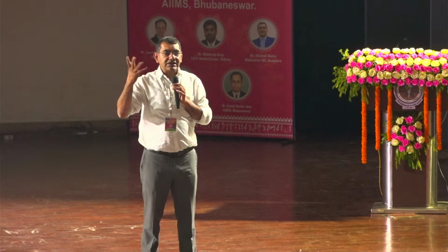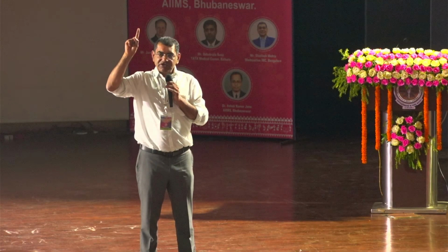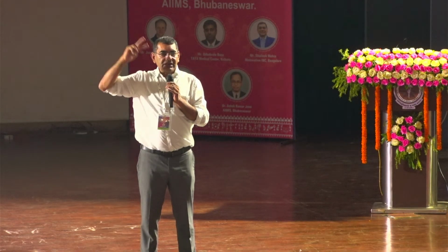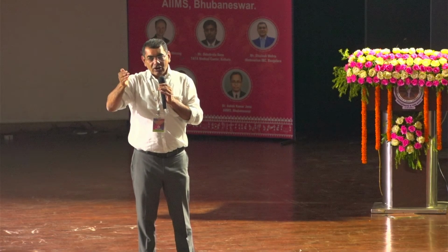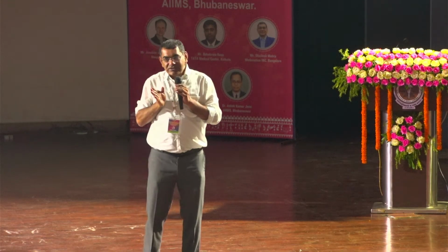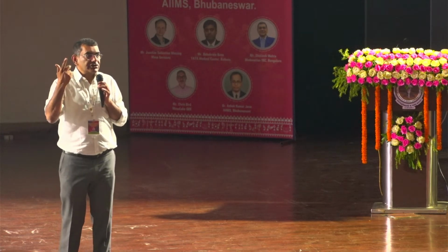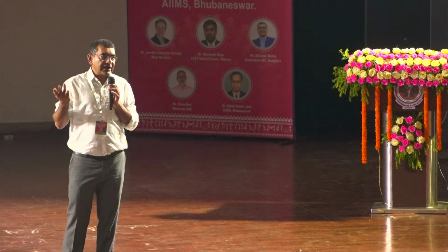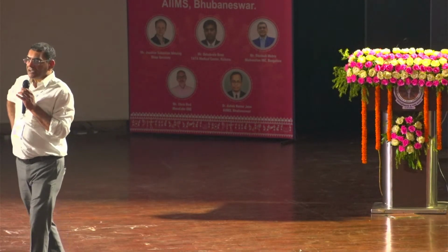इन्फेक्शन कंट्रोल. विदाउट दिस यू बीइंग इन्फेक्शन कंट्रोल इज अ वेस्ट. भुवनेश्वर का प्रेशर कितना है? एटमॉस्फेरिक प्रेशर 1. मिस्टर मेत्सिंग ने सवेरे बोला. तो आपका ओटी प्रेशर 1 बार से ऊपर होना है, नीचे होना है? ऊपर होना है. राइट? ओटी कॉरिडोर का प्रेशर कितना होना है? आउटसाइड प्रेशर से कम. तो उसी हिसाब से माइक्रोब्स ट्रैवल होता है कि नहीं? तो आपको क्रॉस इन्फेक्शन. सो फर्स्ट यू हैव टू अंडरस्टैंड प्रेशर, टेम्परेचर एंड ह्यूमिडिटी. अगर ये 3 मेंटेन नहीं करोगे, एएचयू डालकर फायदा नहीं है. राइट? ऑन दैट बेसिस यू मेंटेन. ईटीयू में कौन सा प्रेशर डालोगे? पॉजिटिव प्रेशर, नेगेटिव प्रेशर?